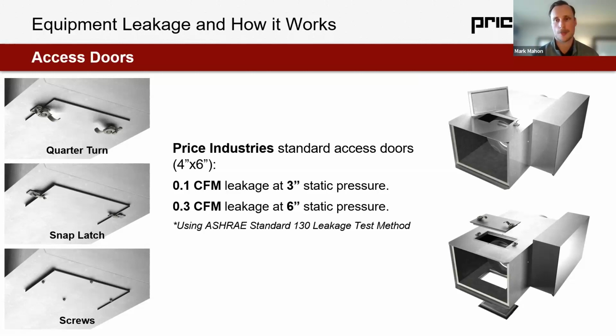And that's actually the reason why Price will be moving forward with adding some language to spec in the springtime, summertime, because we're fundamentally redesigning our access door for more gasket resiliency, a different gasket type, and a larger access door as well. We're going to be moving to a 9x9 access door that is going to be constructed a little differently. It's going to have rounded edges because most of the leakage occurs through corners, and it's going to have a pre-manufactured OEM gasket that's going to be more resilient over multiple cycles of use.